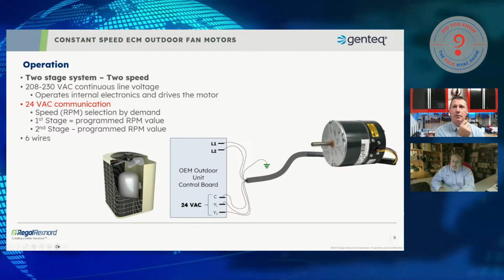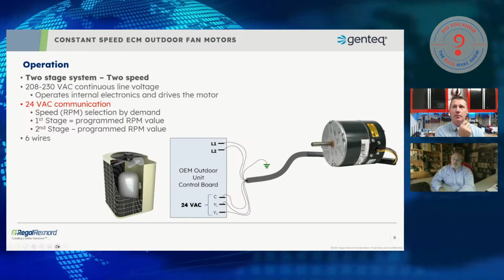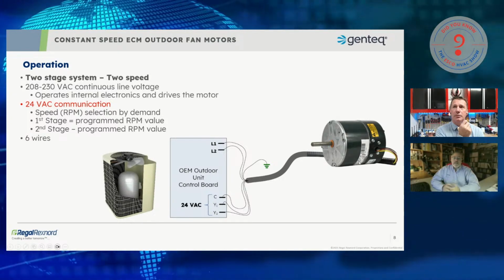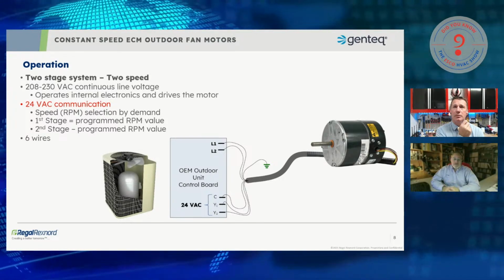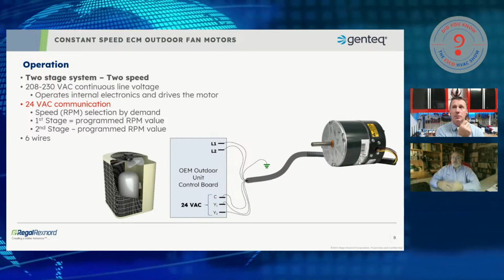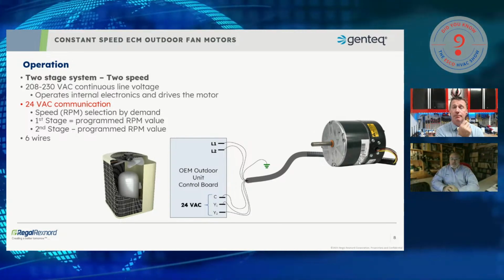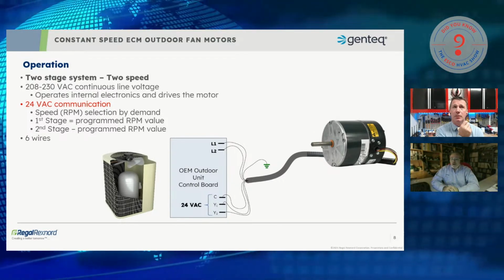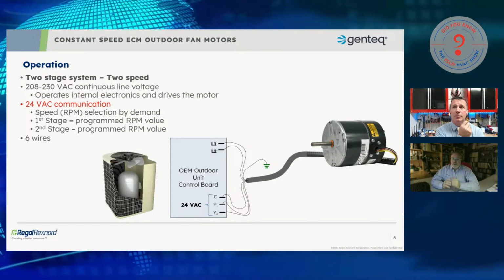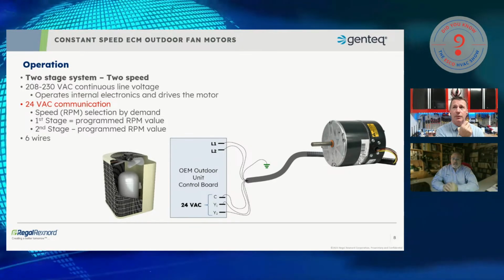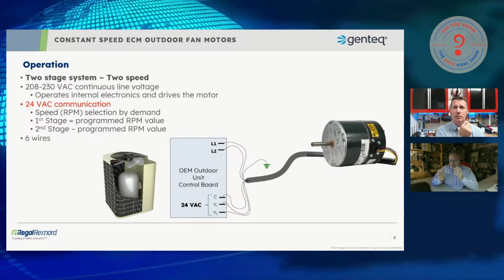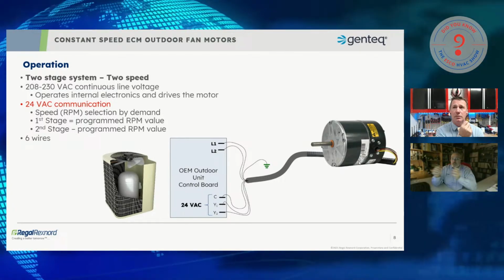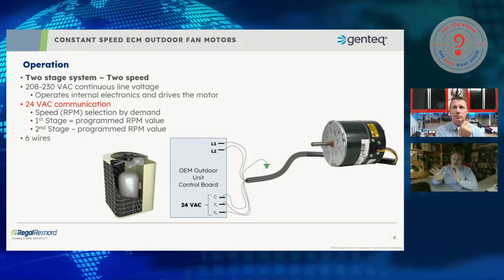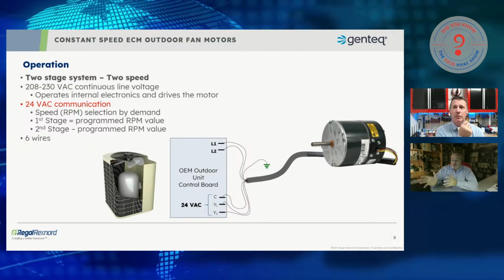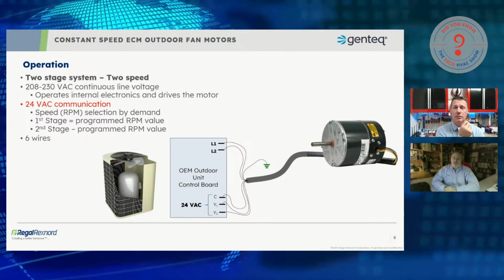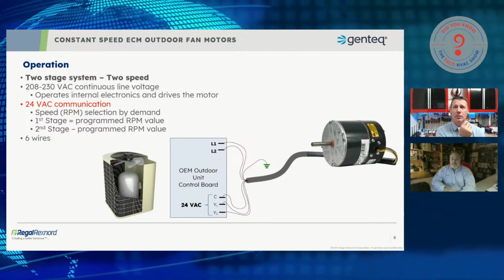You can see a little bit of the rating plate in this picture on the motor. That rating plate could say 850, it could say 1075, it could say 600 to 1200, it could say 1200, but really none of those numbers are 100% guaranteed to be what's programmed into the motor. That's how we tested the motor, how we UL tested the motor. We could then ship that motor to an OEM and they could program it to operate at 1 or 2 speeds that have nothing to do with the rating on the rating plate of that motor.